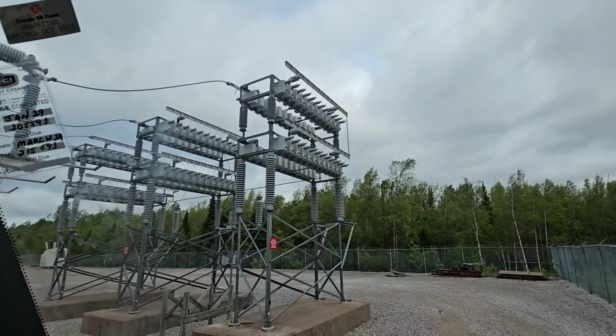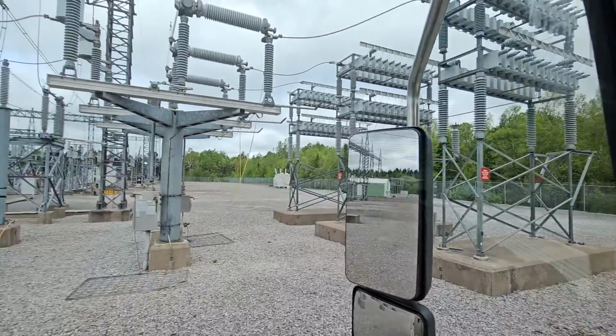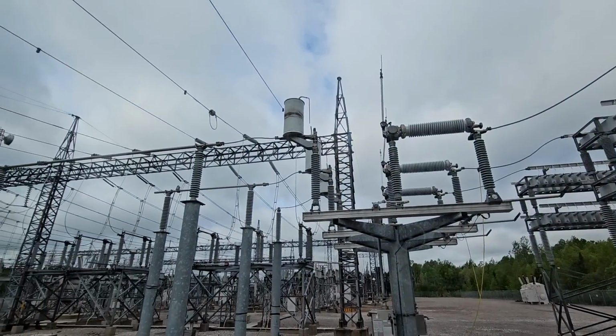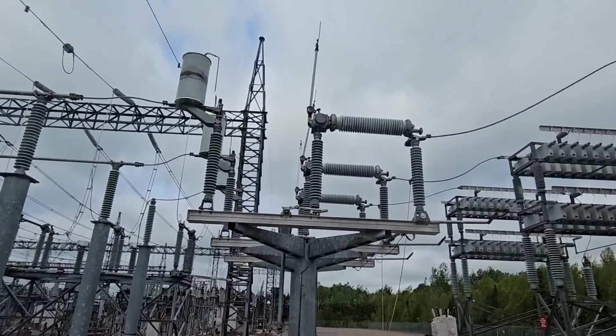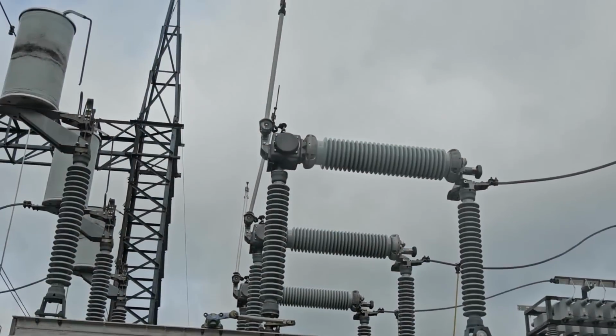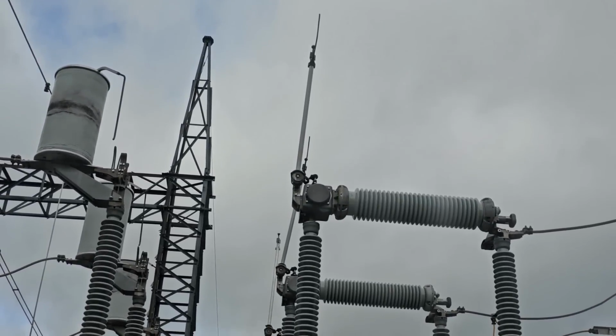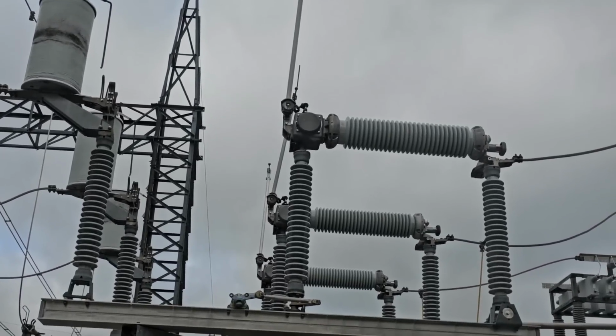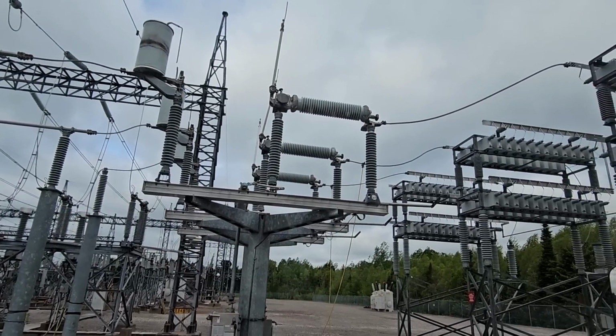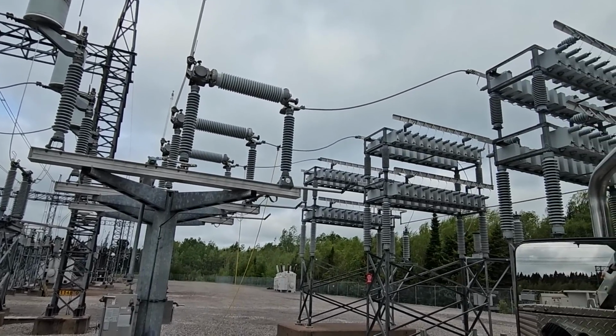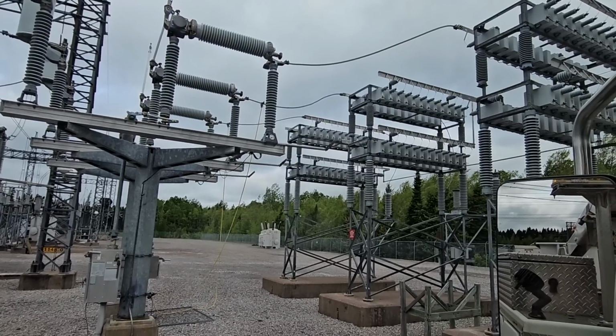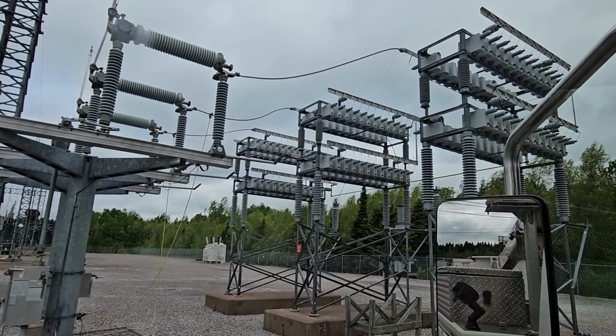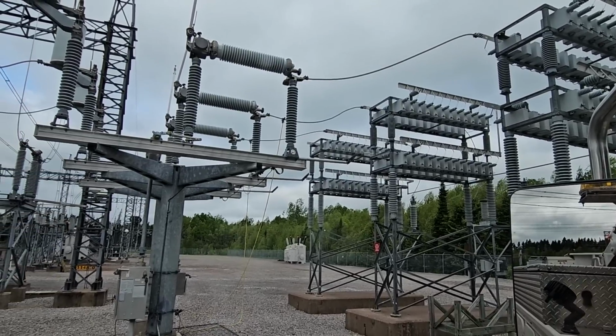But when there's a really bad power factor on the line, this can automatically be closed in from our power system operator. That is an SF6 gas interrupter right here. The disconnect blade's open right now. But that SF6 gas interrupter is required to load break when this capacitor bank is open, because it will draw an arc. There must be maintenance of some sort being done here right now, because that capacitor bank is not online. So typically, as we correct the power factor, it is with capacitors.